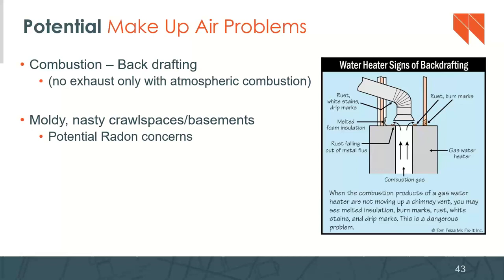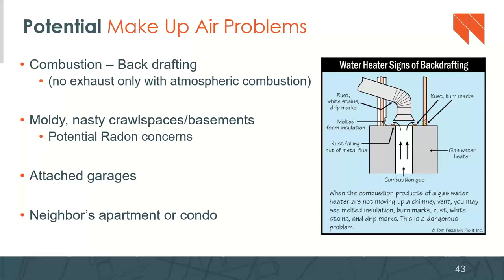It can, again, so talking about where the air comes from in exhaust only, it could potentially come from crawl spaces and basements. It could exacerbate potential radon concerns. If you've got an attached garage, you're negatively pressurizing the home, and so it could potentially bring that air from an attached garage into the home, sort of drive it in there, or maybe from a neighbor's apartment or condo. It's all just getting at this: the space is negatively pressurized with reference to outside or with reference to a different zone of the structure, i.e. the crawl space, garage, your neighbor.